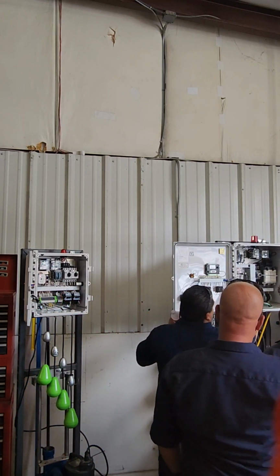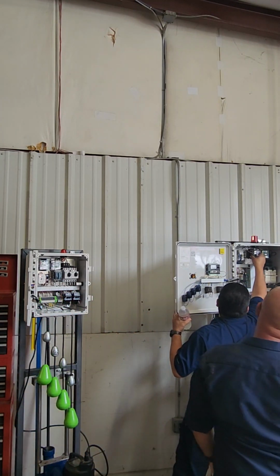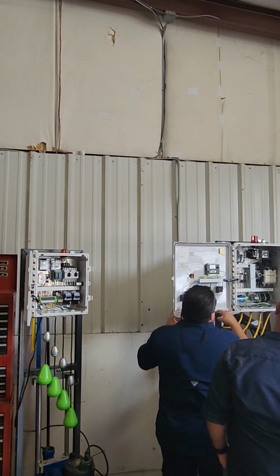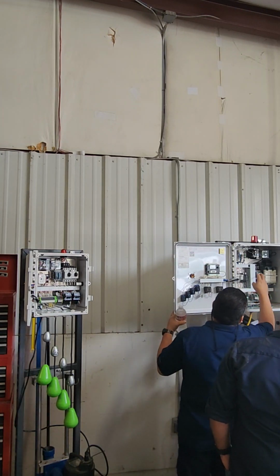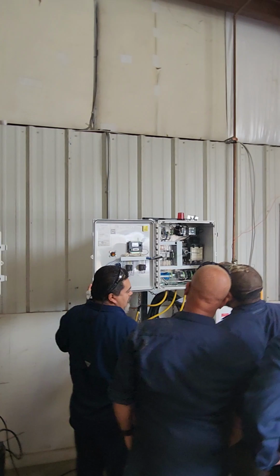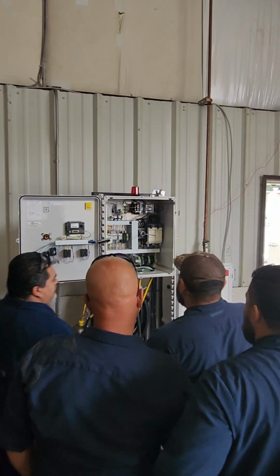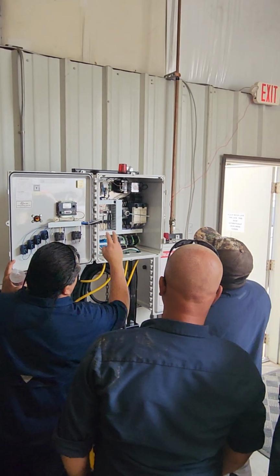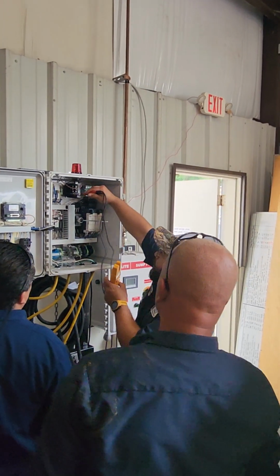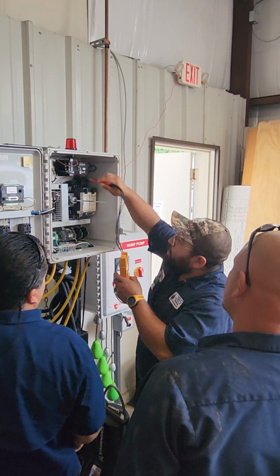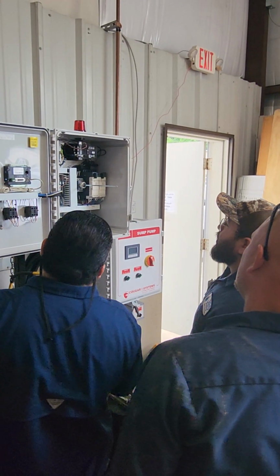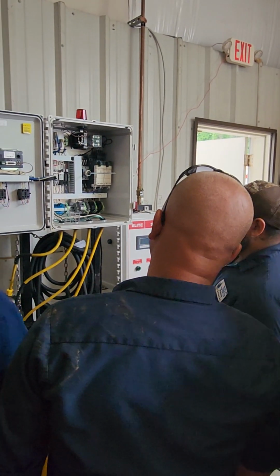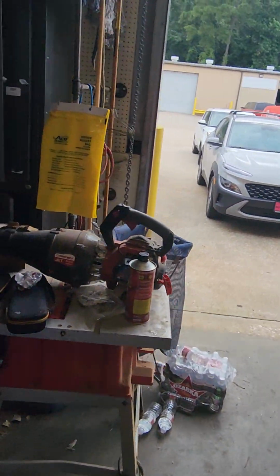Alright, so you've got your fuses up here, right? So you want to check continuity between it. So how do you set your meter? So you will put the leads across each other. You see your sound. So that tells you it's good. Now you see we got power on the pump. So let's say you shut the base power. Now you want to check continuity between the floats. Well, you still get continuity.